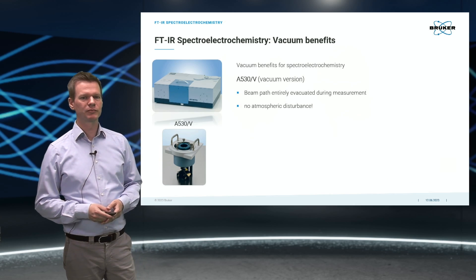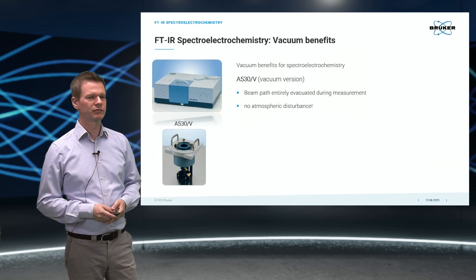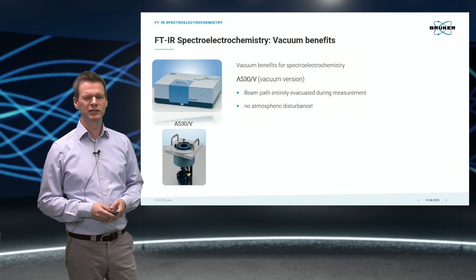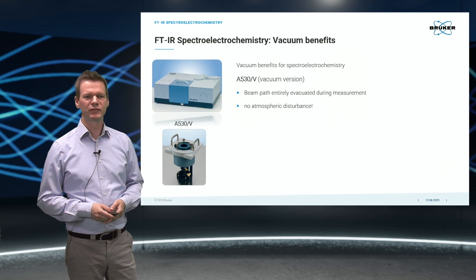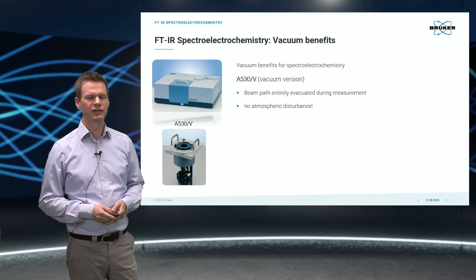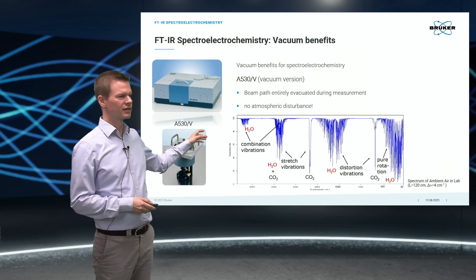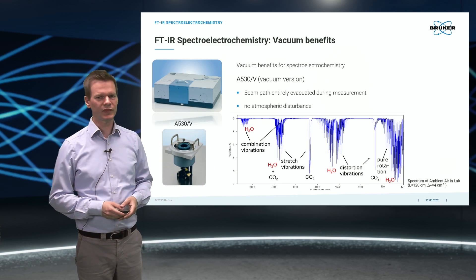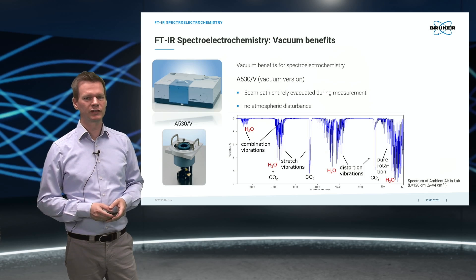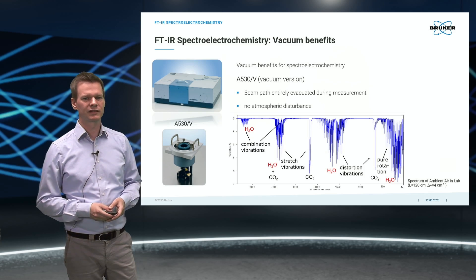Performing experiments on a vacuum FTIR spectrometer gives you big advantages, because the complete beam path will stay under vacuum conditions and no ambient atmosphere will interfere with the IR light. This means the resulting spectra will be free from disturbance of atmospheric carbon dioxide or water vapor, as depicted in the spectrum shown here. This is especially important for organic oxidation reactions where carbon dioxide is a reaction product.